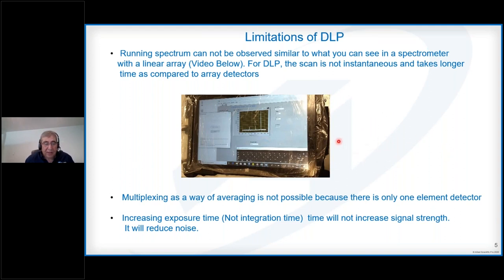The second limitation is that in the case of detector array, you can do multiplexing and boxcar averaging between different pixels, but in case of DLP you have only one single element detector, so you can't do boxcar or multiplexing. The other difference is for small signals, the array detectors can increase the integration time and amplify the small signal. But in case of DLP, there is no integration time, there is only exposure time. Increasing the exposure time does not increase the amplitude of the signal. It has more time to do averaging, which can help reduce the noise, but it doesn't amplify the signal. These are some of the limitations.